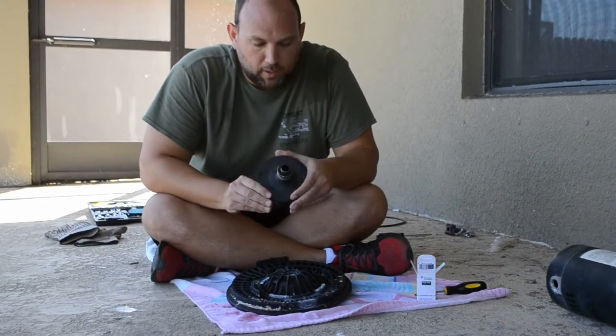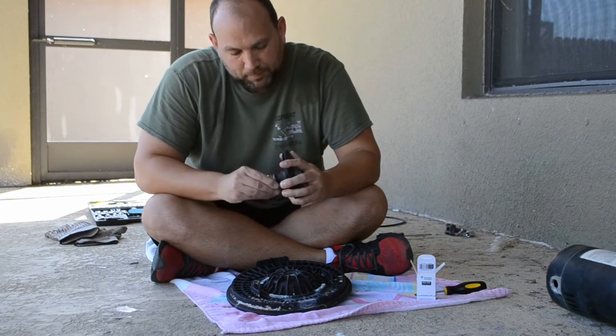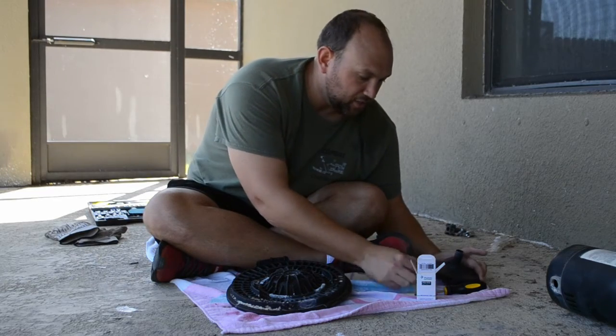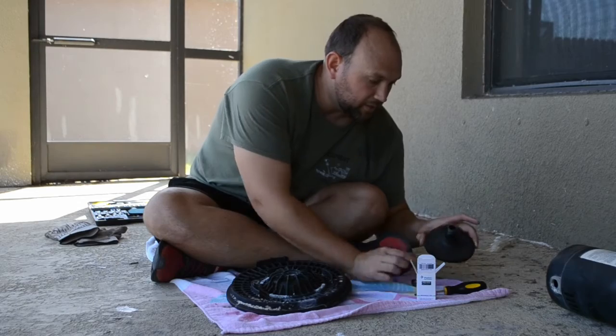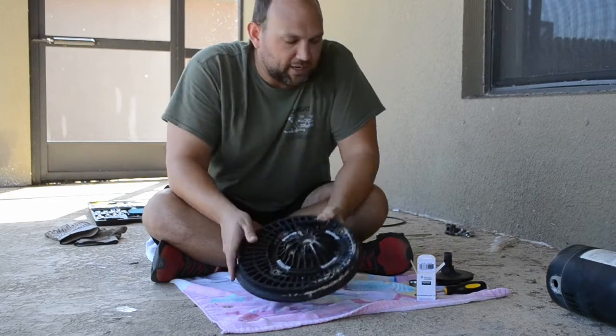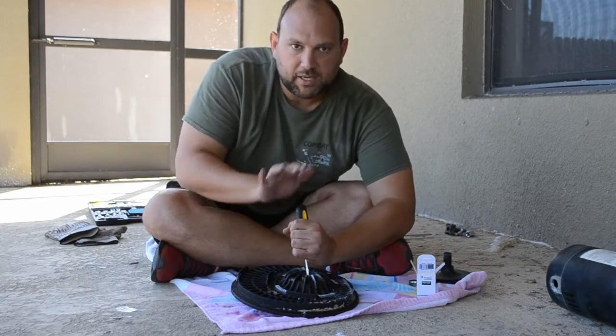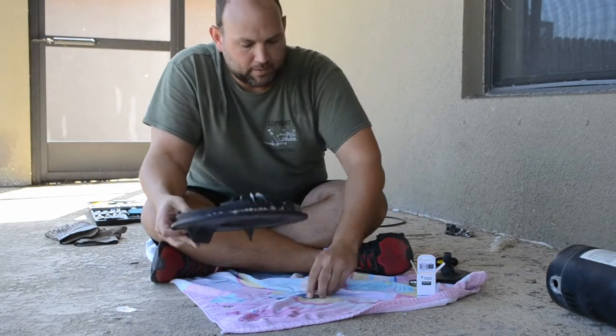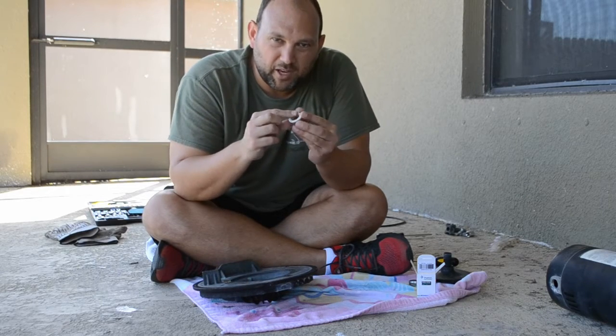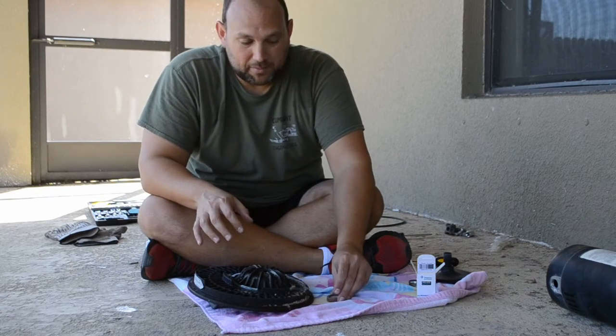I'm going to remove these two. I've noticed the spring is towards the lower half of the impeller — and that actually pulled off really easily. I'll just leave it in the same orientation next to it so I have something to look at. For the other portion of the shaft seal, I'm going to take a flat-head screwdriver, set it up in the back, and just hit it with the back of my hand. Remember, we noted the white portion was actually facing upwards — and that's how easy it is to remove it.